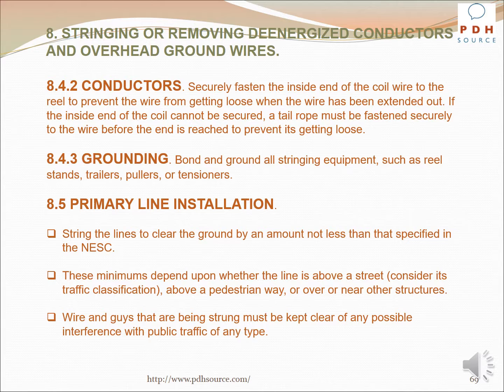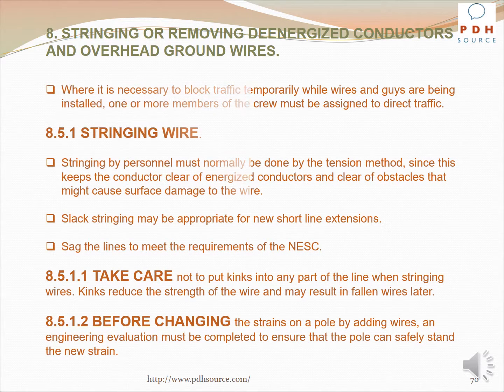Wire and guys that are being strung must be kept clear of any possible interference with public traffic of any type. Where it's necessary to block traffic temporarily while wires and guys are being installed, one or more members of the crew must be assigned to direct traffic. Stringing wires by personnel must normally be done by the tension method, since this keeps the conductor clear of energized conductors and clear of obstacles that might cause surface damage to the wire.